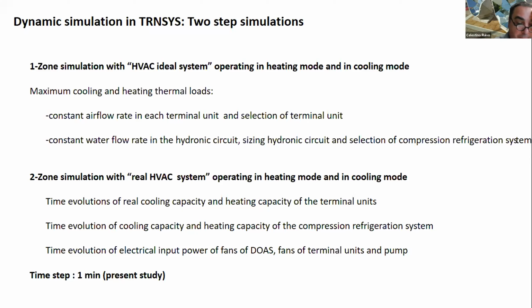Firstly, the air conditioning system was simulated for both operating modes, considering the ideal system of TRNSYS, with the main goal of finding the peak loads that are needed to determine the airflow rate, to select the terminal units, and to determine the water flow rate in the hydronic circuit, to size the hydronic circuit and to select the compression refrigeration system.